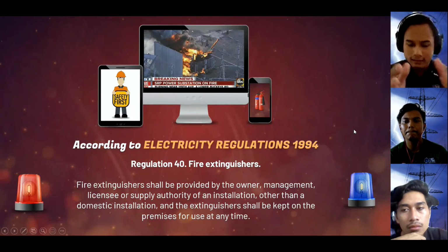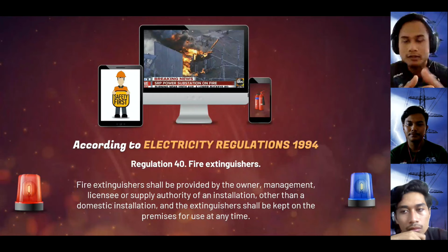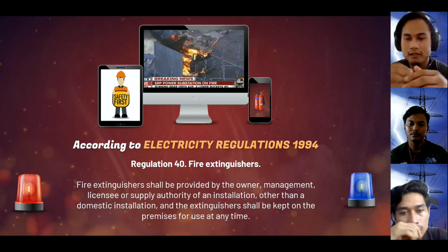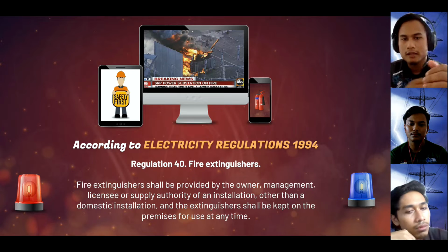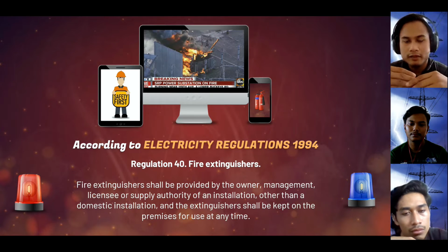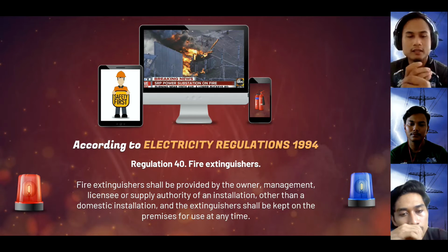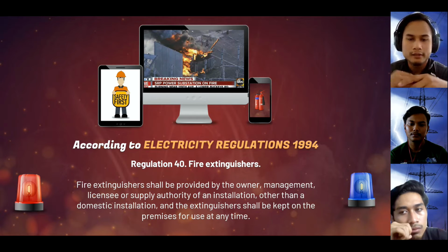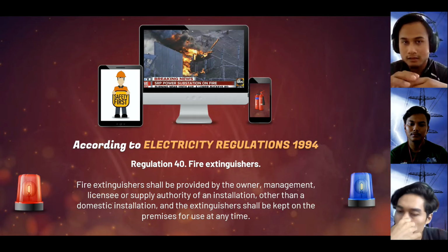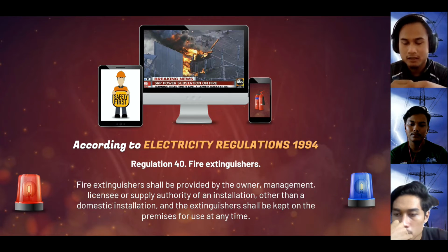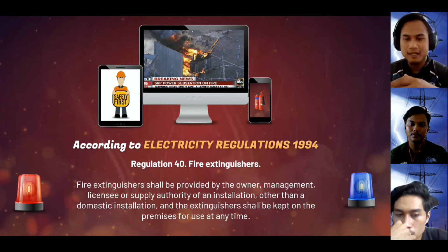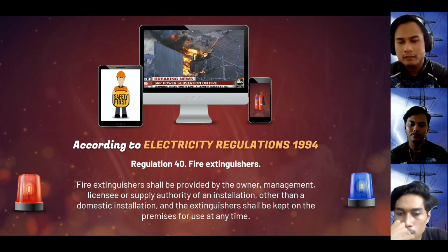And of course this does not follow the electricity regulation, because according to the Electricity Regulations 1994, regulation 40 mentions that a fire extinguisher should be provided by the owner, management, licensee or supply authority of an installation other than a domestic installation, and the extinguisher shall be kept on the premises for use at any time.